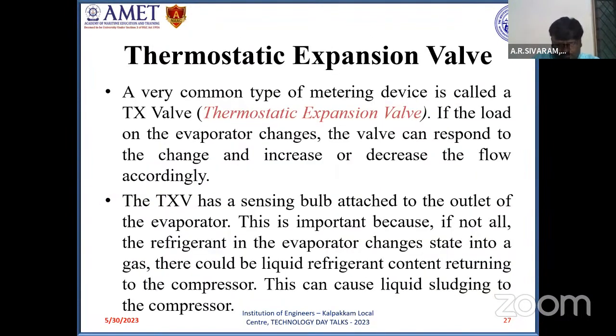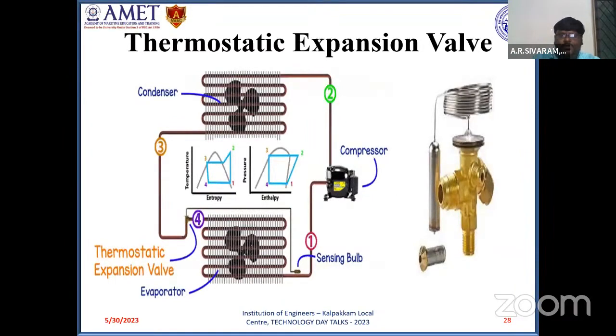Coming to the expansion device, this is the thermostatic expansion valve. The thermostatic expansion valve alters the mass flow rate of refrigerant depending upon the changes in the indoor unit. Say one person is present in a room, or 40 persons are present in a room. If 40 persons are present in a room, obviously the cooling load is more. If one person is present in a room, obviously the cooling load is less. So with respect to the changes in cooling load, the thermostatic expansion valve alters the mass flow rate of refrigerant.